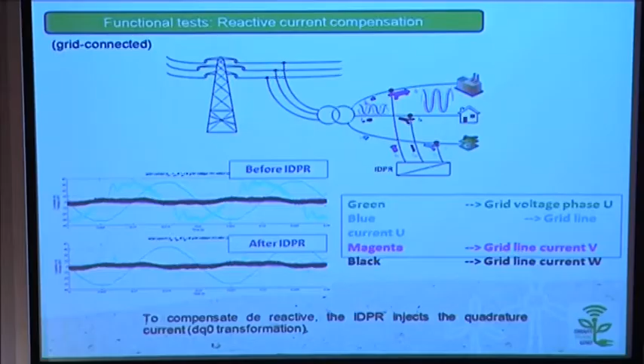Then another thing, and this maybe represents in the best way the concept of routing. Imagine that we have a system. These are the 3 line currents. 2 phases are with almost no load, and one has some current. The IDPR has the capability to say, okay, I'm going to consume in a balanced way the currents from the line side, from the DSO side, and then I'm going to supply just what I need at the load side. So this means that we are routing the energy. For example, we need 10 amps of current in phase A, but we are consuming from the grid side approximately 3.3 amps per phase.